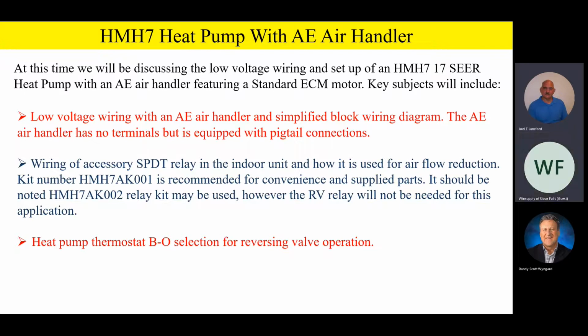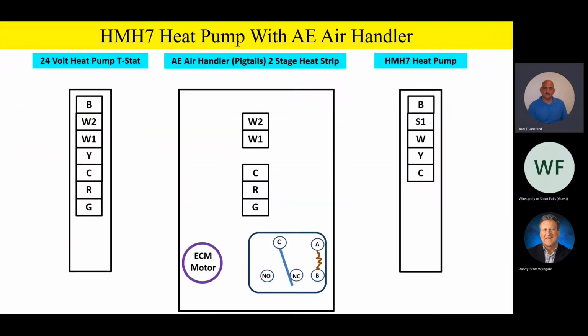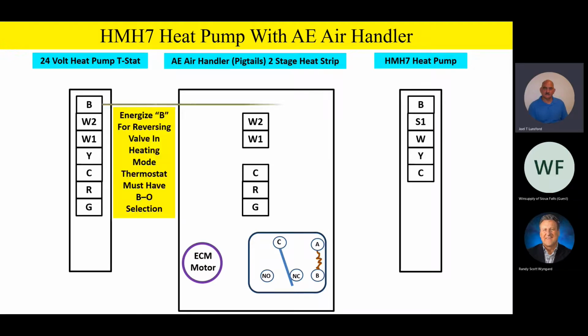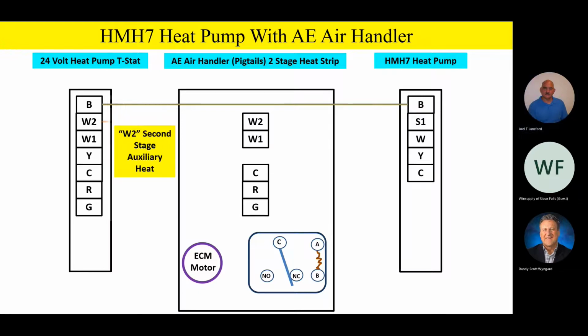Okay, sounds good. So let's take a look at the AE air handler with just a standard 2-stage heat strip. In other words, you're going to have a W1 and a W2 for auxiliary heat call. And so from the thermostat to the outdoor unit, we're going to have that B terminal going straight outside. Now, what that's for, again, is we're going to energize the reversing valve in the heating mode. And so that thermostat has to have that BO selection, so you can select heating mode of operation on the reversing valve with that B terminal. W2 is your 2nd stage auxiliary heat if you've got a 2-stage heat strip, and that's pretty straightforward. Just W2 to W2 would be the normal hookup on that.